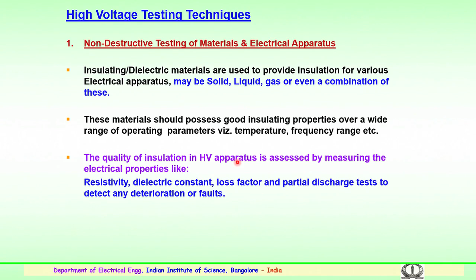The quality of the insulation used in high voltage apparatus is generally assessed by measuring the properties of these materials, solid, liquid or gases, or a combination of them, by measuring the resistivity of a material, the dielectric constant, loss factor, what we know as tan delta, capacitance and tan delta measurements, and partial discharge testing, the internal discharges which could happen in the materials, and also to find out any defect or deterioration. These are a few of the things generally carried out for the non-destructive testing of materials, conducted in the laboratory or at the manufacturer's place to assess the properties of the materials.